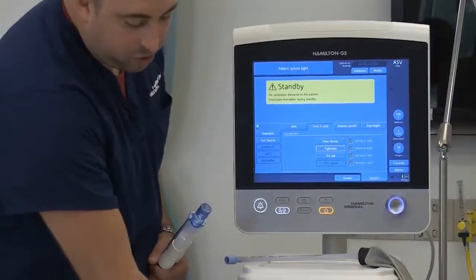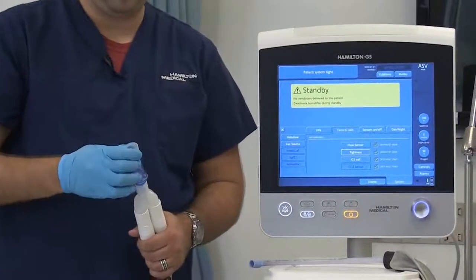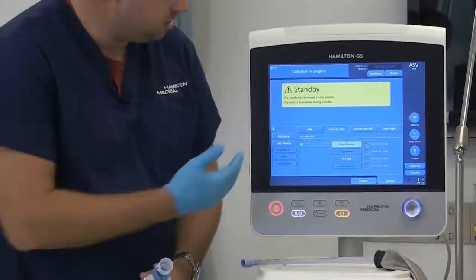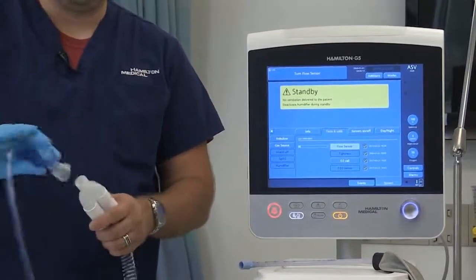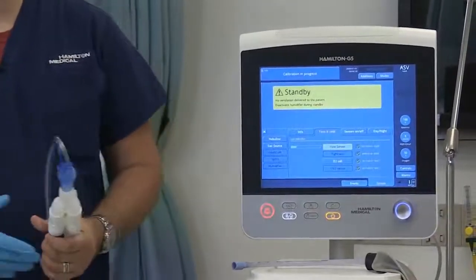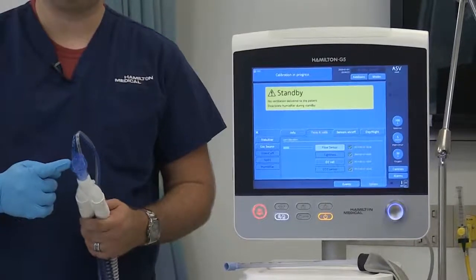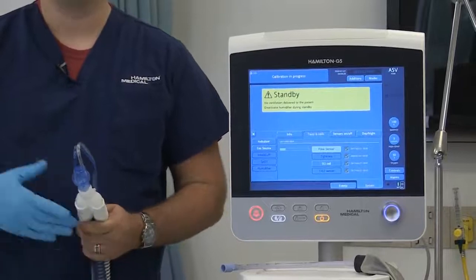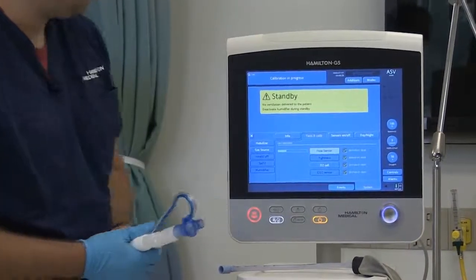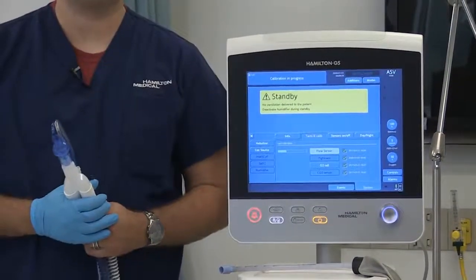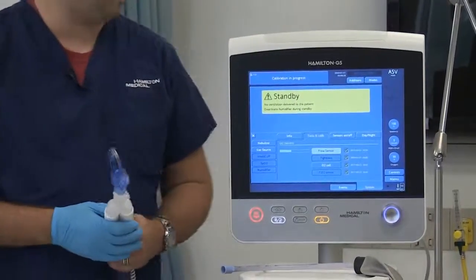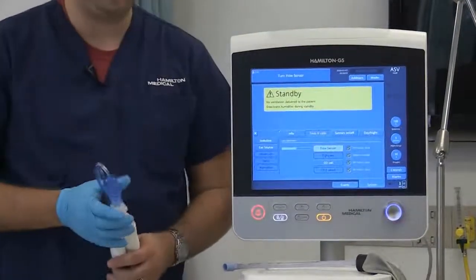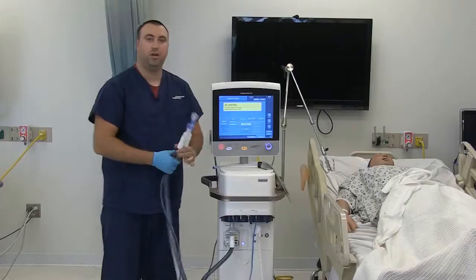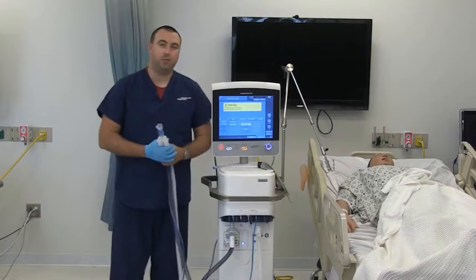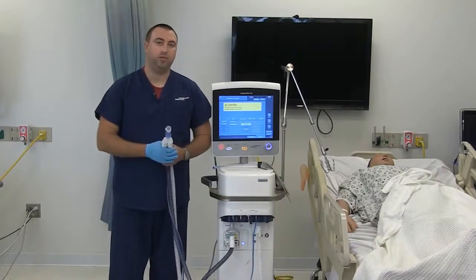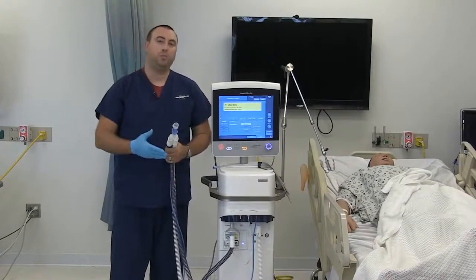Flow sensor would be next. For the flow sensor, every flow sensor comes with this piece. So press flow sensor, and again, you will be prompted up here to turn the flow sensor. So you would flip it around like this. And the flow sensor test will take about 20 or 30 seconds on this orientation. And then on the other orientation, when you flip it back around, it'll take another 20 or 30 seconds. The O2 cell, we only recommend calibrating when prompted to by the machine. Up here you'll see turn flow sensor again. So turn it back around. Every time you get prompted to do something by the ventilator, it will give you 15 seconds to do so, or it will cancel the calibration and mark it as a fail.